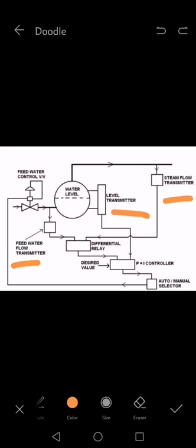Now let's say your boiler is running and suddenly you open a steam valve in some zone. The steam demand has increased. Let's say you opened heating for the fuel oil bunker tank. Now steam is also flowing to the bunker tank, which is a very heavy use tank, so there is a sudden increase in the demand of steam.